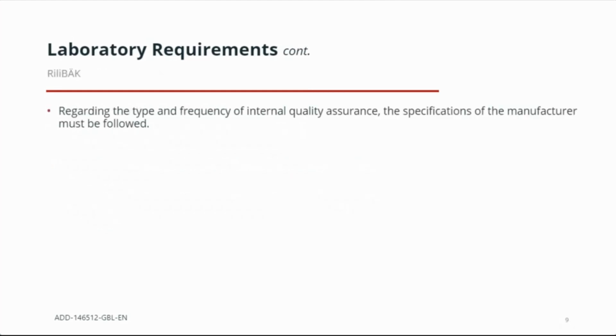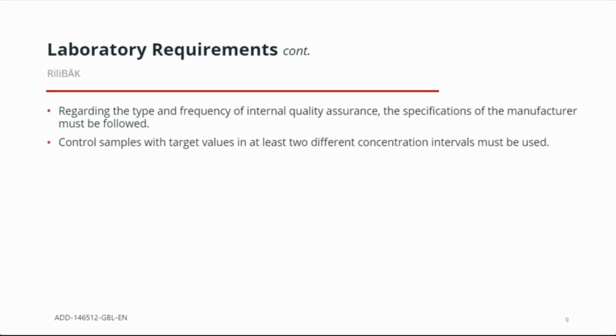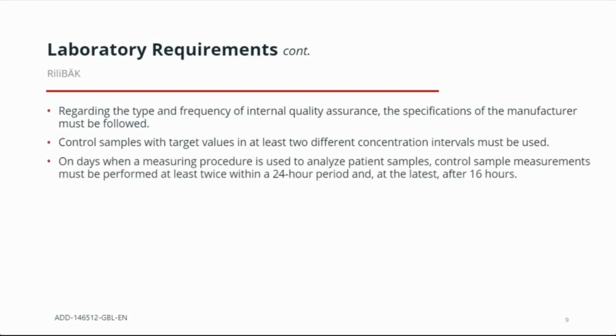The RiliBÄK regulations are specific to Germany. There are other country-specific regulations, but we won't have time, unfortunately, to address them all. We will dive into this one a little bit. It states that the type and frequency of internal quality assurance and the specifications of the manufacturer must be followed. Control samples with target values in at least 2 different concentration intervals must be used. Each day of patient testing, control sample measurements must be performed at least twice within a 24-hour period, and at the latest after 16 hours.